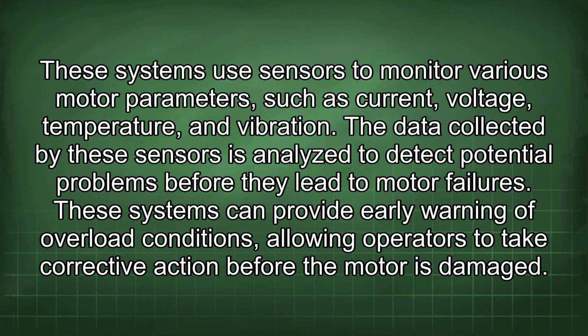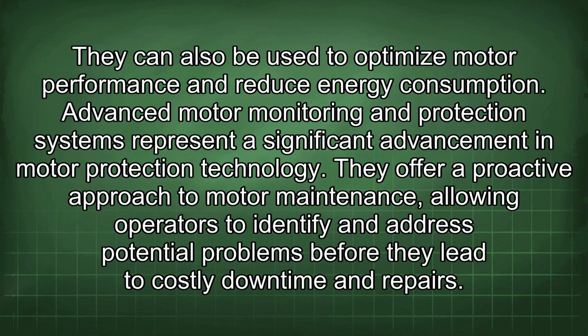These systems use sensors to monitor various motor parameters such as current, voltage, temperature, and vibration. The data collected by these sensors is analyzed to detect potential problems before they lead to motor failures. These systems can provide early warning of overload conditions, allowing operators to take corrective action before the motor is damaged. They can also be used to optimize motor performance and reduce energy consumption. Advanced motor monitoring and protection systems represent a significant advancement in motor protection technology. They offer a proactive approach to motor maintenance, allowing operators to identify and address potential problems before they lead to costly downtime and repairs.